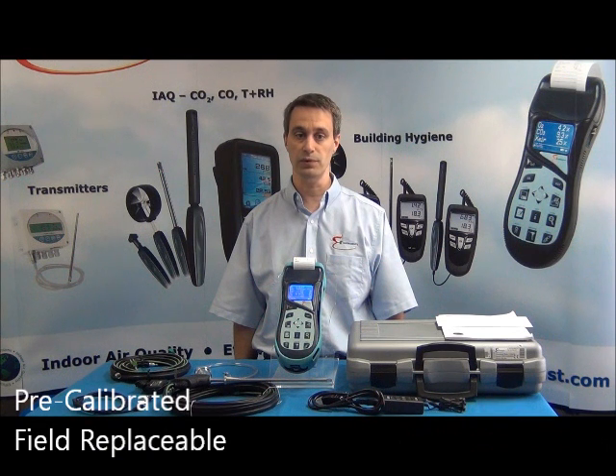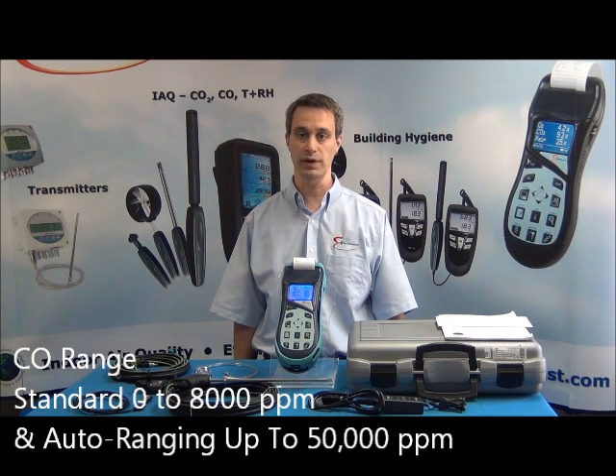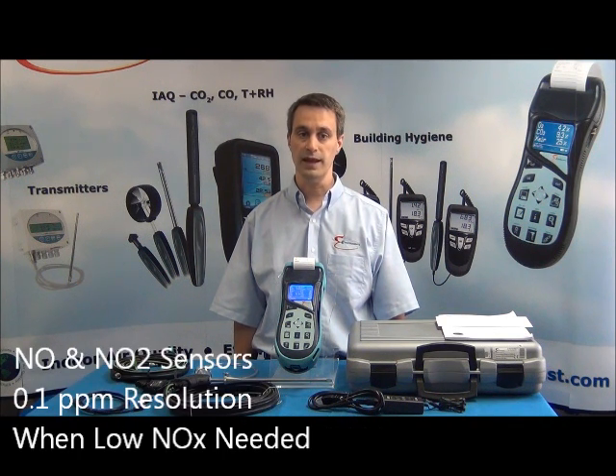The gas sensors are pre-calibrated and easily field replaceable, which will minimize analyzer downtime. The CO sensor has a normal measuring range of 0 to 8,000 ppm. The sensor also has an auto-ranging feature that allows for CO measurements up to 50,000 ppm using a dilution pump. The NO and NO2 sensors can be configured for low ranges with 0.1 ppm resolution when low NOx is needed.